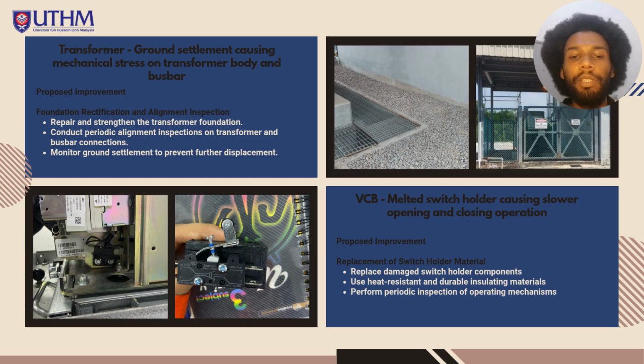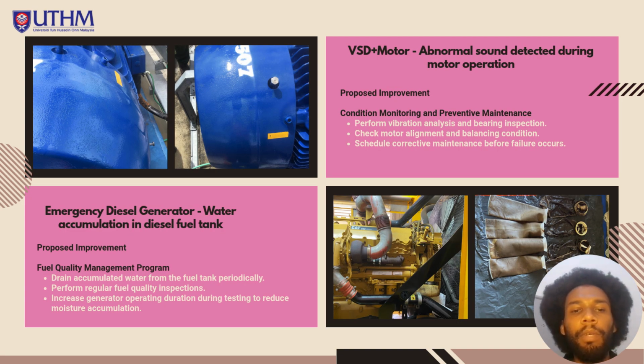The repeated inspection of the operation mechanism should be included in the preventive maintenance program. So these three improvements will improve reliability and reduce the risk of unexpected failure. Okay, for the motor system, condition monitoring technologies such as vibration analysis, alignment inspection, and bearing monitoring should be implemented. These methods allow early fault detection before serious damage occurs.